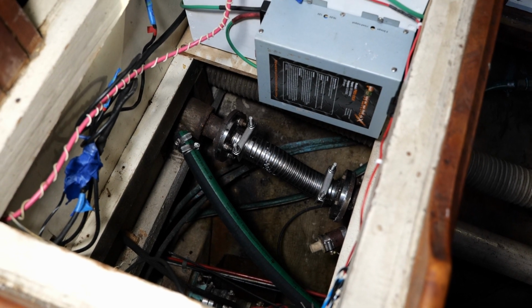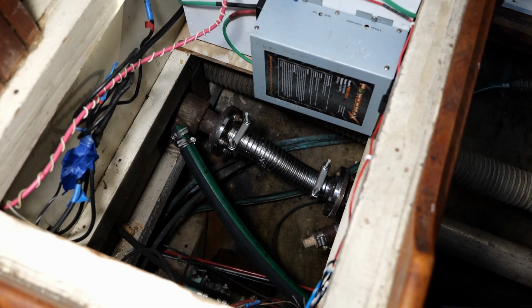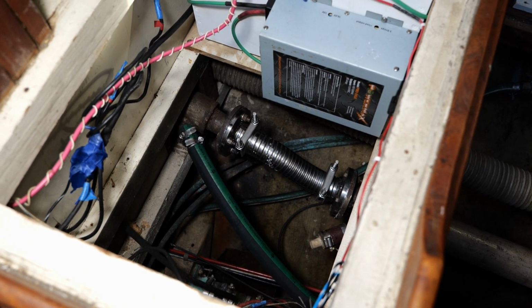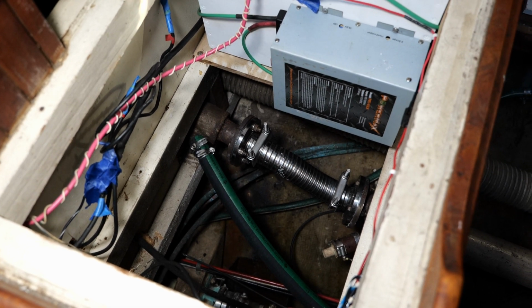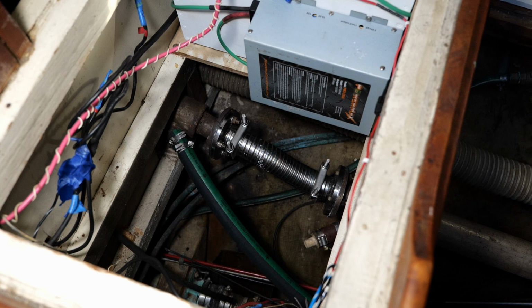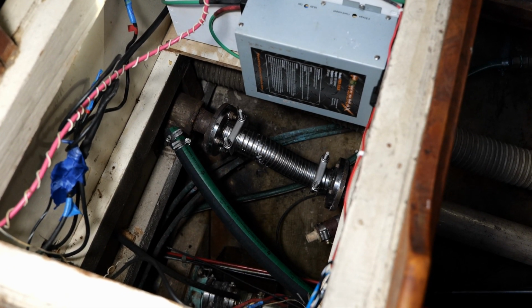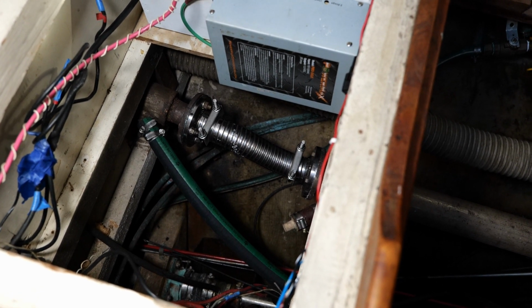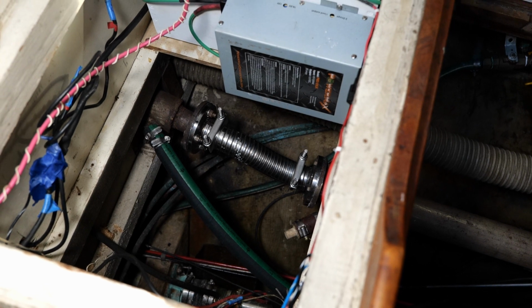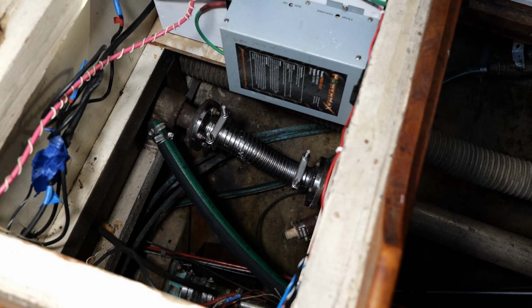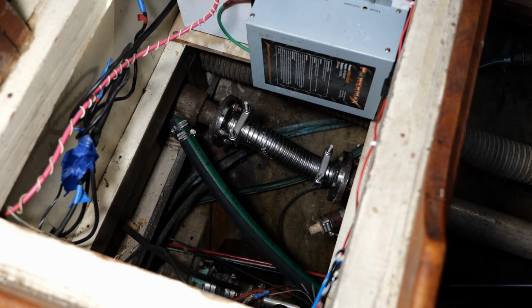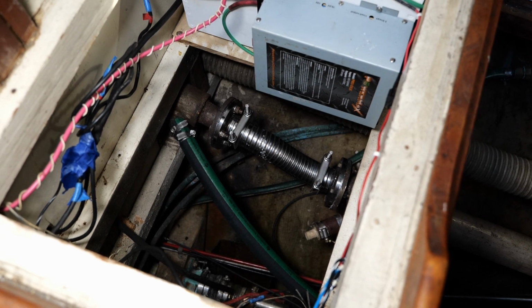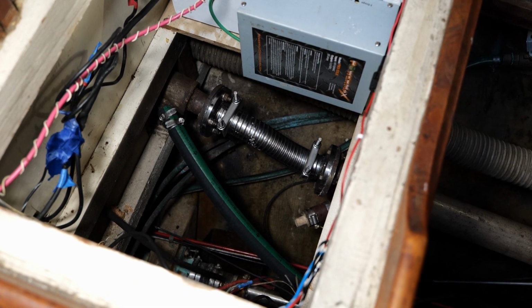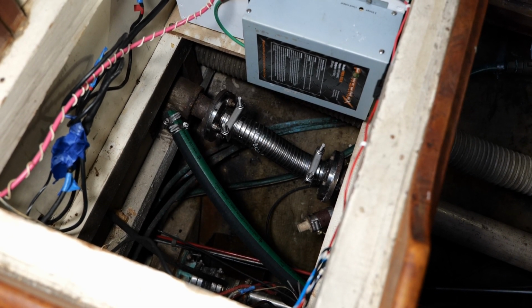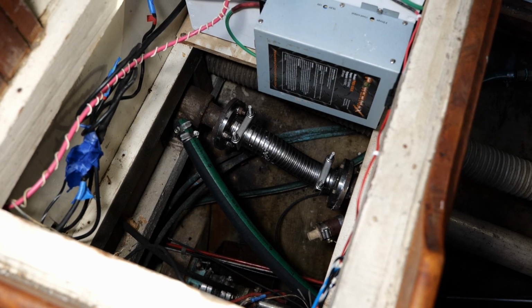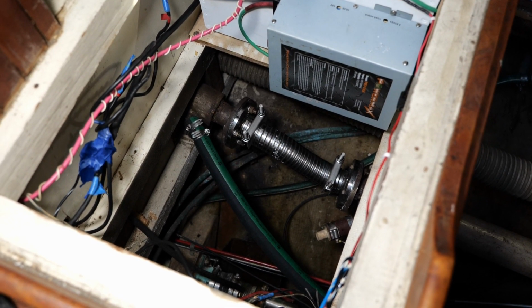I just tightened up the U-bolts again, and it didn't really seem to help much. As for the flanges themselves, with the graphite gaskets, you torque them down to 20 foot-pounds of torque, and I don't have a torque wrench. It would have been hard to get in there with one anyway, even the ratchety kind - you definitely couldn't get in there with the bendy kind. But the other way you can tell if the gaskets are crushed down tight enough is you crush them to 50%. When I used just a box wrench on tightening those, I know I was putting more than 20 foot-pounds of pressure on, and it didn't crush hardly at all, so it's not 50% on the crush.